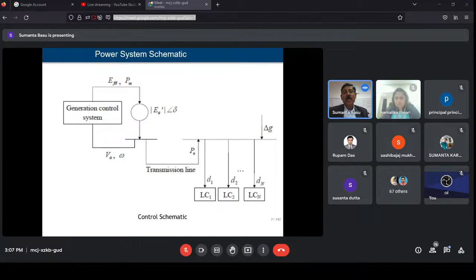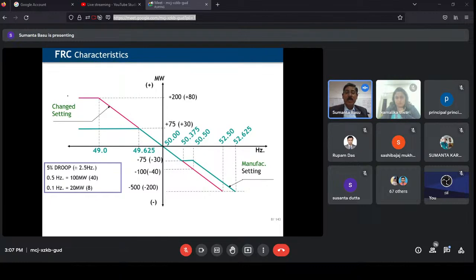So you must be aware that during COVID time and after that also there were 2 incidents where the entire country's lighting load came down, as per the appeal of the Prime Minister of India. Though the lighting load comprises a very small percentage of total grid load, still before going to that, a lot of simulation studies happened, so that switching off the lighting loads of the entire country doesn't destabilize the power system network.